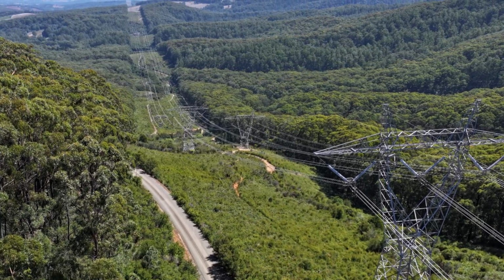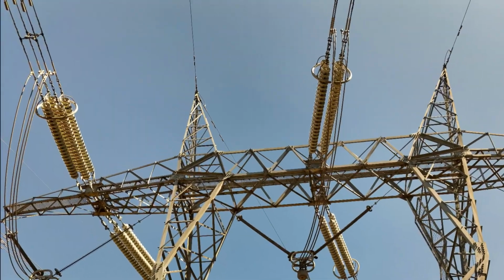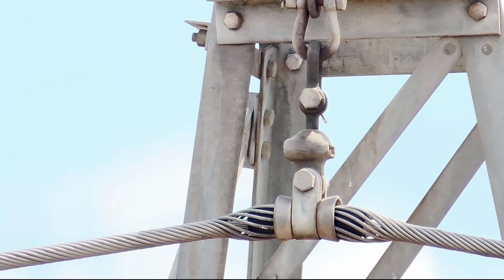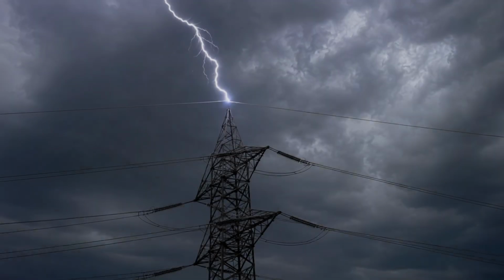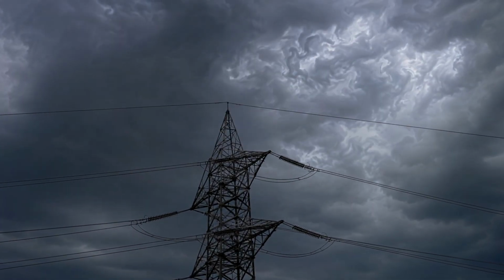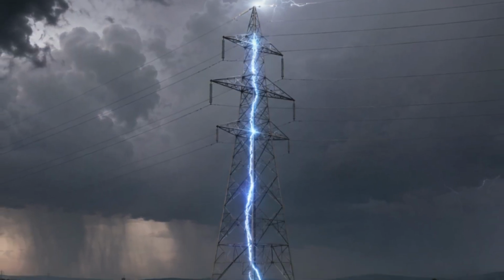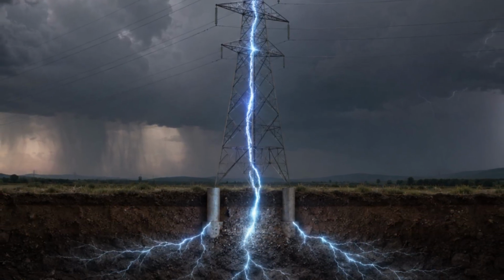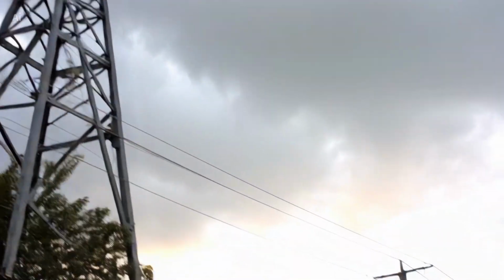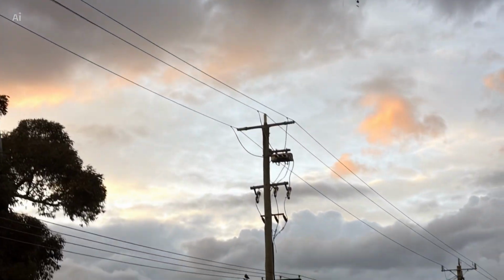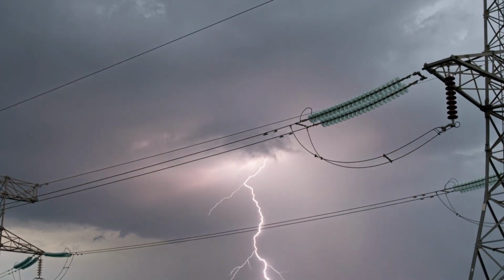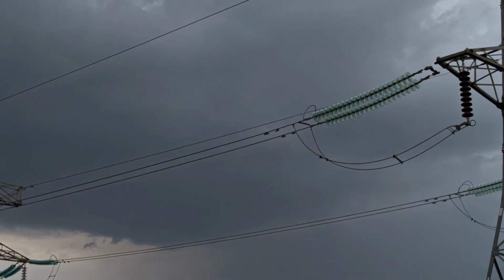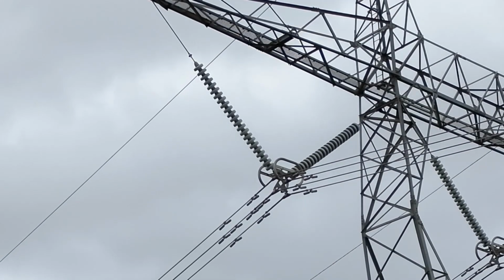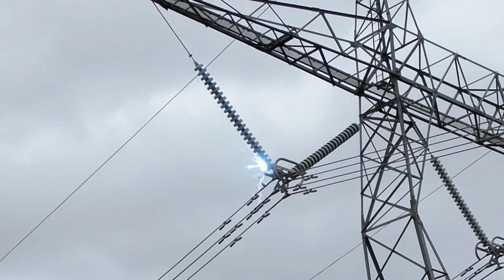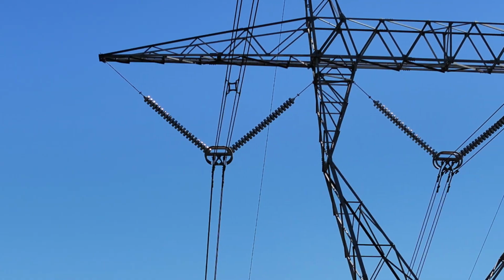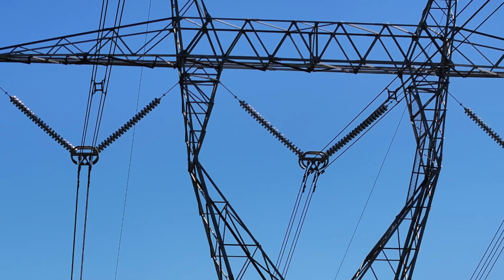On many large transmission towers, one or two thinner wires sit above the main power lines. They are placed there to be hit first. If lightning strikes one, much of the energy can travel down the tower and into the ground. But not every line has the same protection, and no system catches every strike. Lightning can still hit a live wire, or it can hit the tower so hard that electricity jumps across the insulators, the parts that keep the live wires away from the steel.